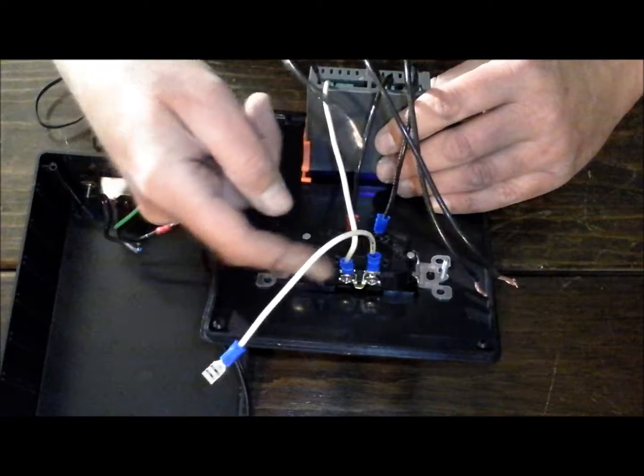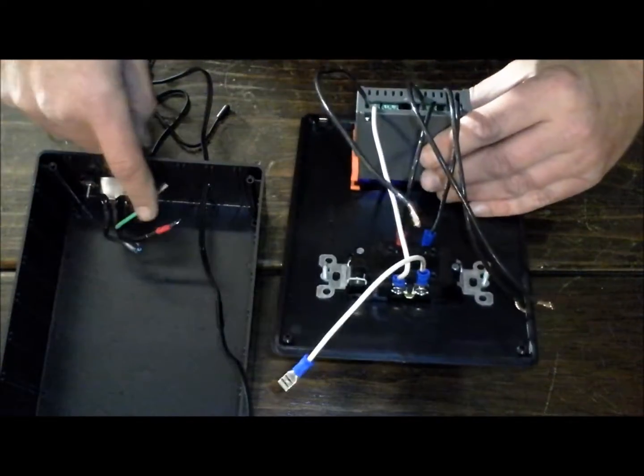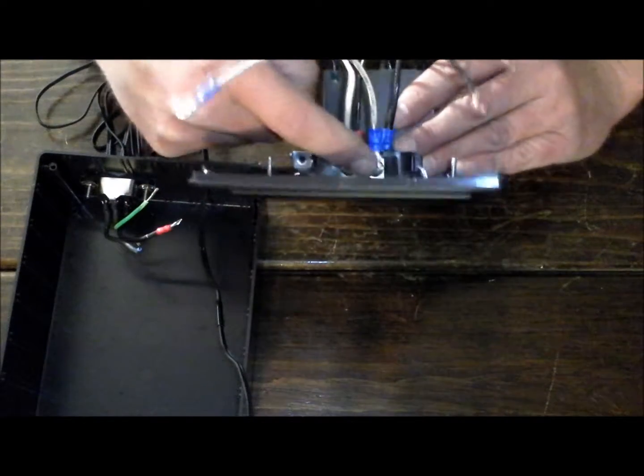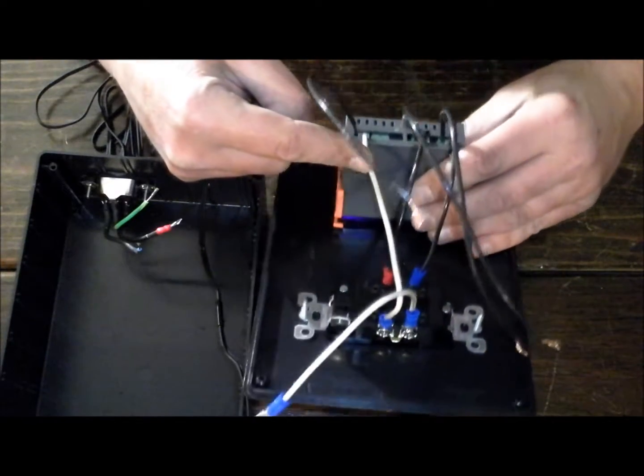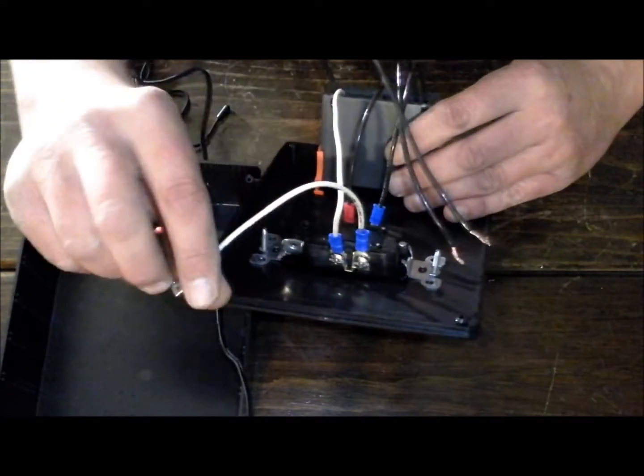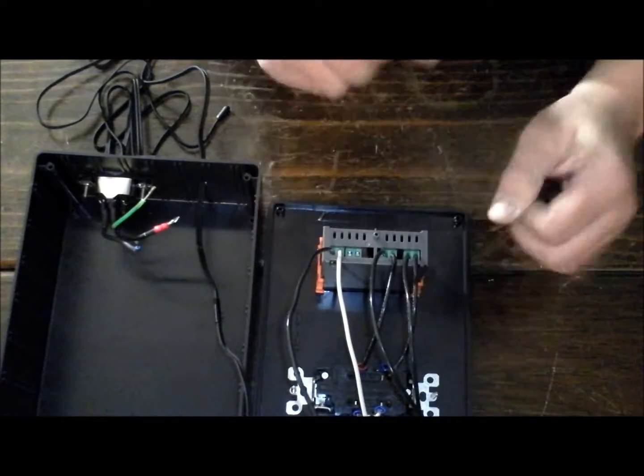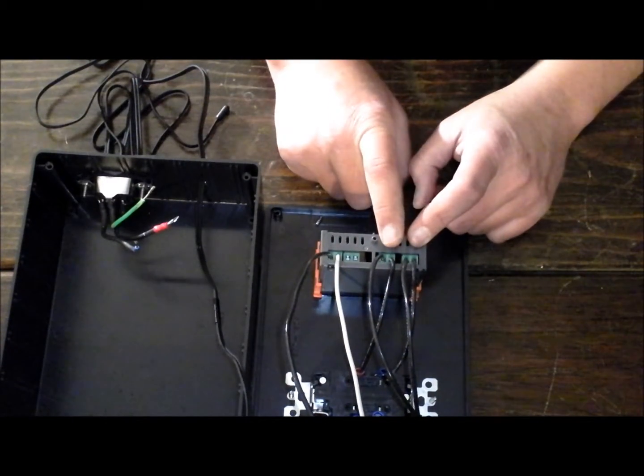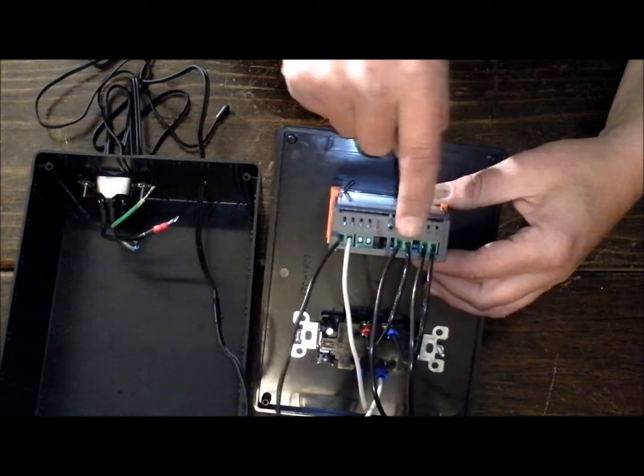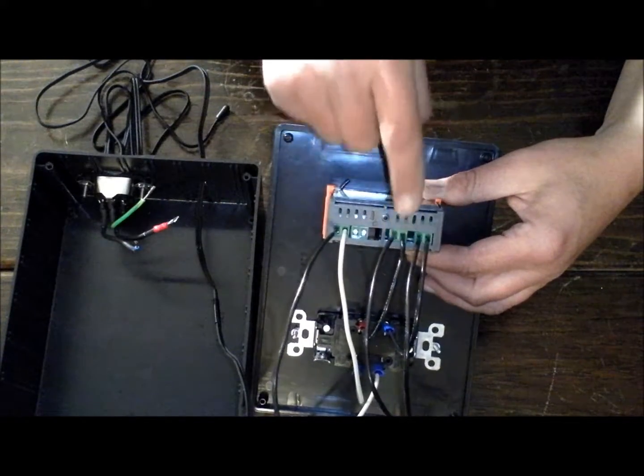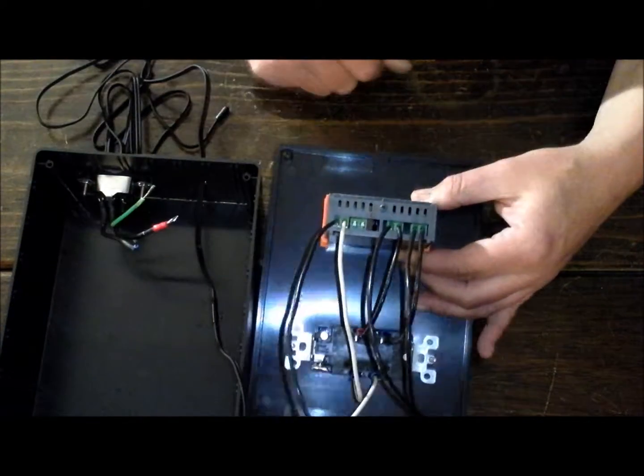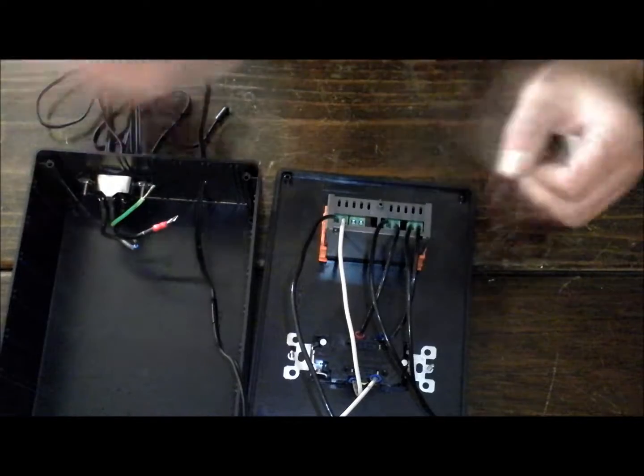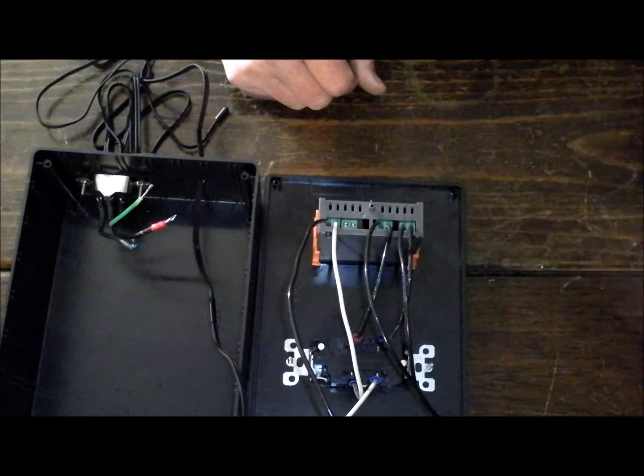Your common wire, this is going to connect to our main common or neutral coming in from our box. And then we didn't break the tab on this so we can connect the other side to here and that common is just going to come up and power our unit. This is also going to serve as the common side for our outlet. So that's really all there is to the wiring, it's not real complicated. The biggest mistake I think people make with these units is thinking that this power in for this is actually a hot and a neutral and it's not. It just acts as a switch, they're both hot wires, one coming in and one going out to your outlet. So now I'm going to connect all this up and we'll put it together, plug it in and hopefully it'll light up and do what we want it to do.